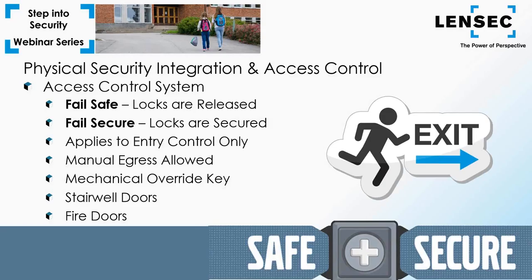Most doors default to fail safe; design documents will specify if fail secure is required for specific doors. Fail safe locks should be used on stairwell doors requiring reentry and any other doors that should allow free access upon a fire alarm or power failure. Fail safe electric strikes should not be used for stairwell reentry because fire doors require a fail secure electric strike for positive latching. It's critical for fire doors to stay closed during a fire — fail secure is used on these doors to provide structural barriers preventing fire from spreading throughout a building.